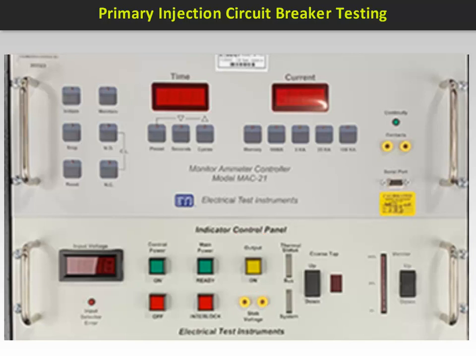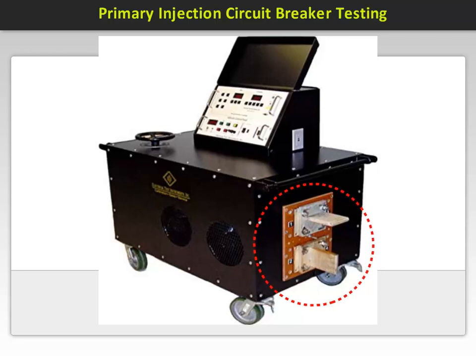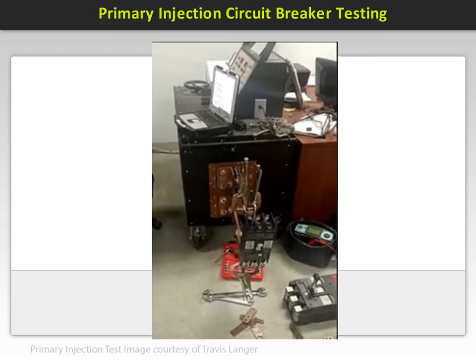Output power on light is right here. The output transformer supplies the bus on the test set, which can be set at 208, 240, and 480 volts, and is capable of generating currents up to 6000 amps. The output power is available on the bus stabs located on the side of the test set. It is important to note that the test cables need to be sized for the proper current of the device being tested. This image shows a molded case breaker connected during a test. The set can also be used on insulated case breakers and low voltage power breakers.